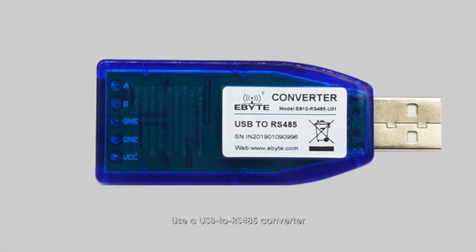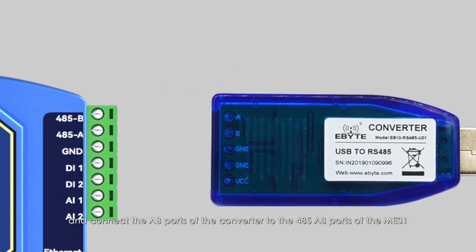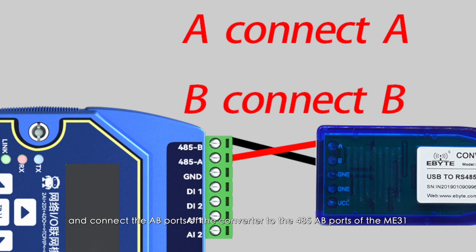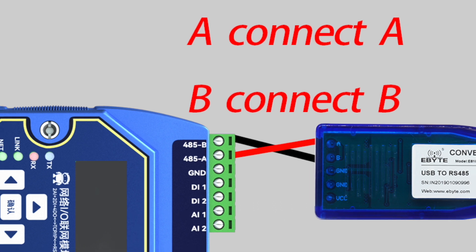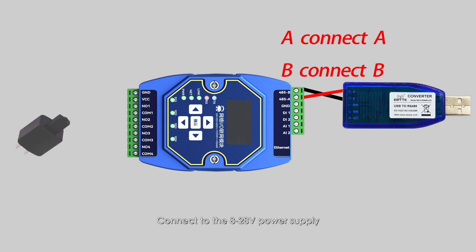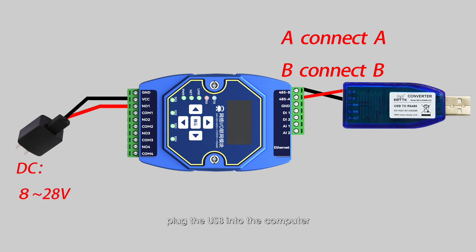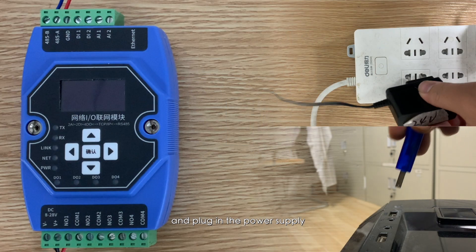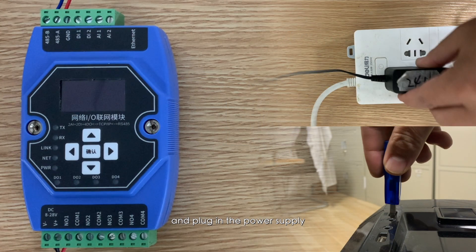Use a USB to RS485 converter and connect the A/B ports of the converter to the 485 A/B ports of the ME31. Connect to the 8-28V power supply, plug the USB into the computer, and plug in the power supply.